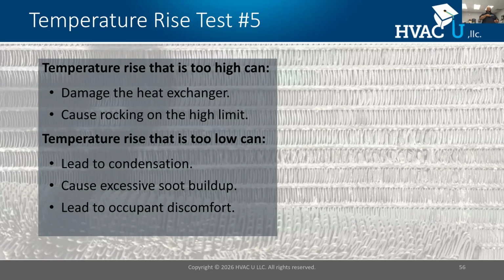I see novice technicians make a mistake where if a limit switch fails, they'll replace the limit switch but not address the airflow problem. So it's something to look at. Over a long period of time, we can get damage to the heat exchanger. Remember that crack we talked about, that annealing? If we damage the heat exchanger, that can come from not enough airflow and high temperature rise. If it's too low, that can lead to condensation in exhaust gases, which is acidic. It can damage our exhaust piping for certain appliances, cause soot buildup, and also lead to customer discomfort, which isn't good either.